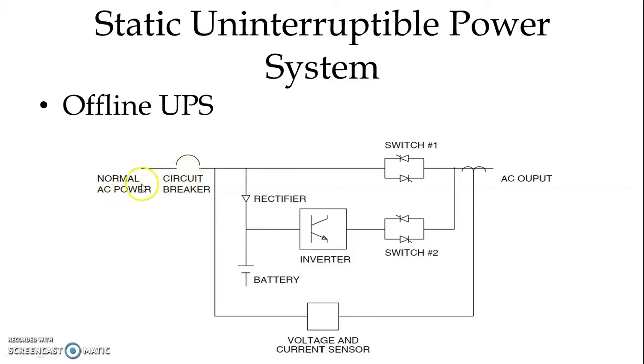So in case of availability of normal AC power, through the rectifier our battery remains charged. In case of loss of normal power, the load is switched to the battery through the inverter. So battery now will supply to the inverter, and inverter will convert DC power into AC power to supply our critical load. We have static switch.